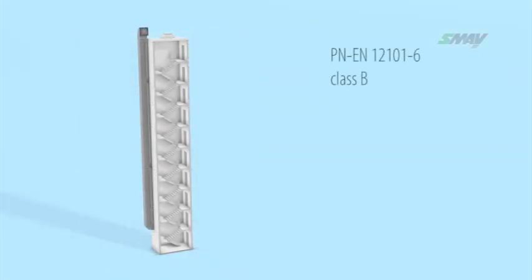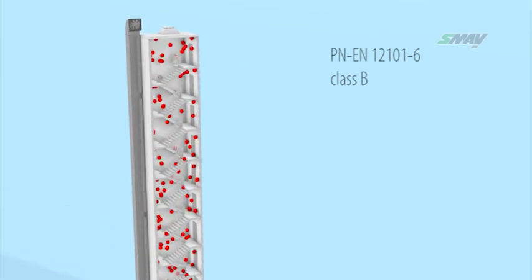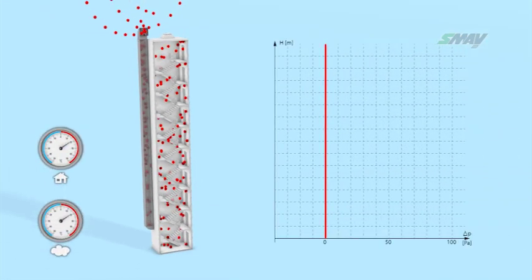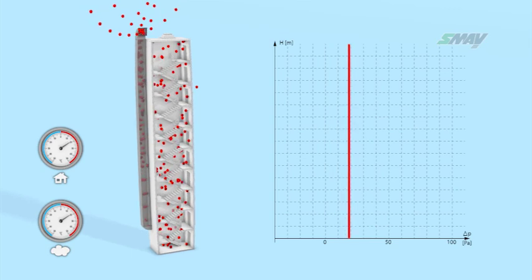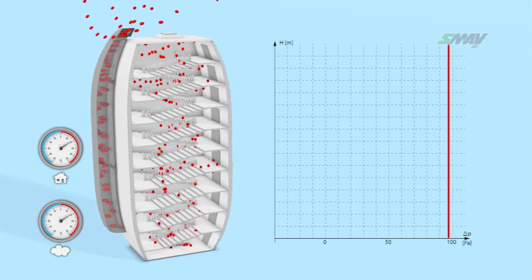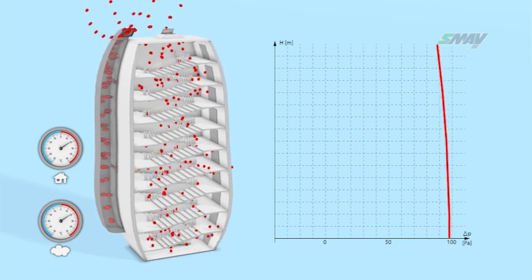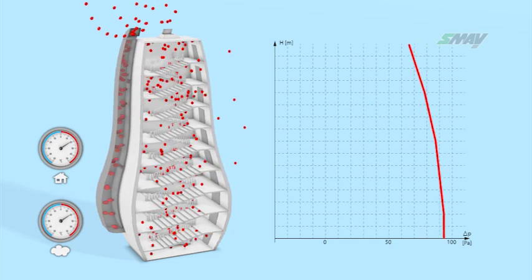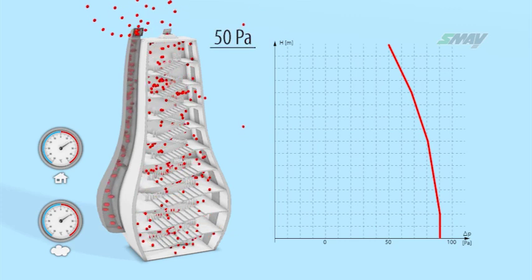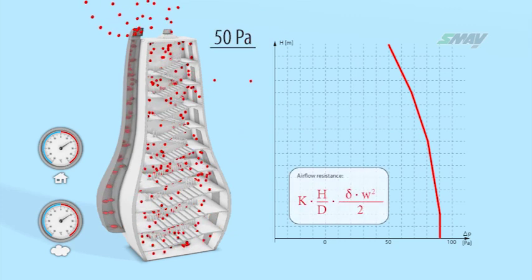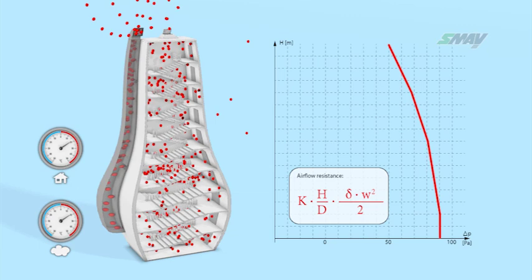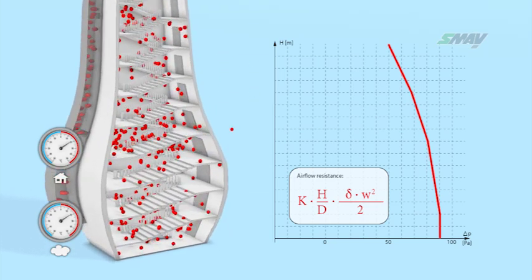If the building incorporates a class B solution in accordance with the EN 12101-6 standard, requiring large amounts of air, then injecting the stairwell with air at the same temperature as the air inside the stairwell would initially cause a violent pressure spike along the entire height. The excessive pressure rise causes the barometric overpressure damper to open, maintaining overpressure in the upper parts at 50 pascal. The flow of large amounts of air causes resistance similar to normal ventilation ducts, and due to this resistance in the lower sections, overpressure exceeds the allowable value, which may make evacuation impossible.